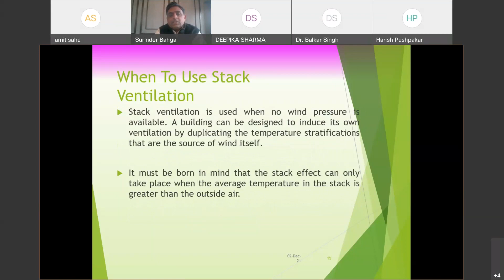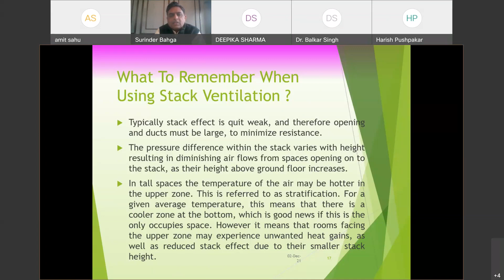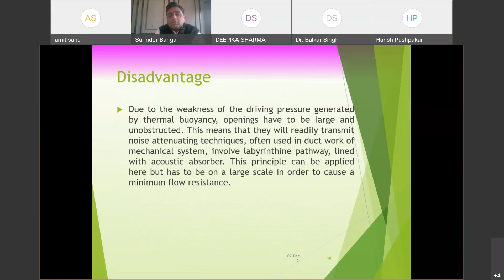Stack effect is not very strong because we are relying on the pressure differential created by the temperature difference of the air. So it requires a very critical balance of the architecture and the studies, wind pressure studies, wherein you can create it. If it is not done properly, it can go horribly wrong. So though it's a very good concept, and was used well in olden days, these days many people are not using it. Like I explained, the weakness is that the driving pressure is generated by thermal buoyancy, which is very difficult to obtain. Then cross ventilation.